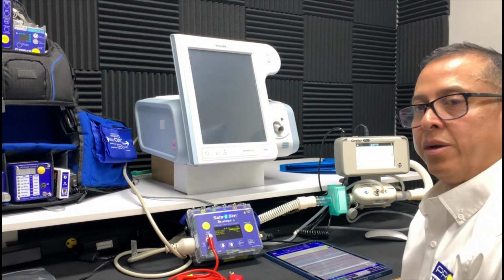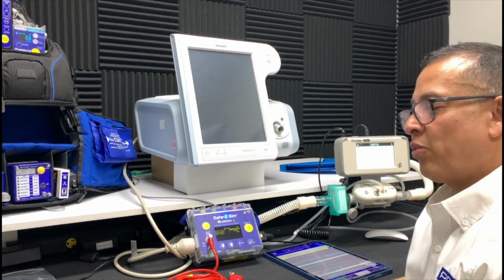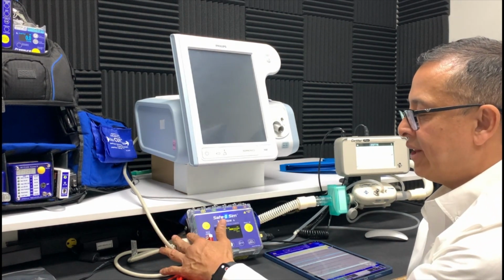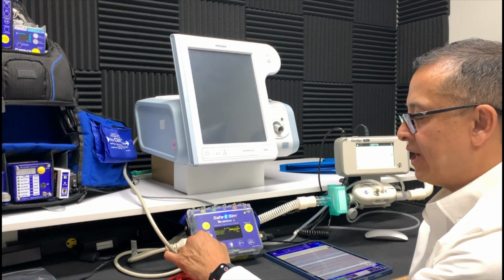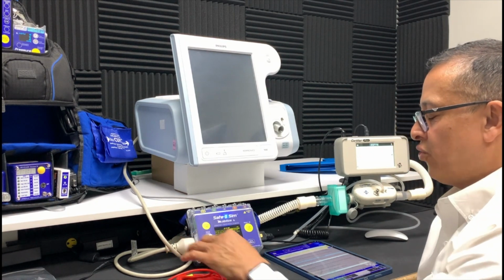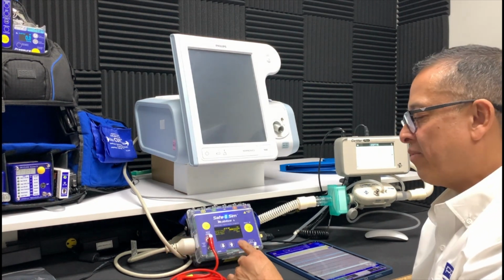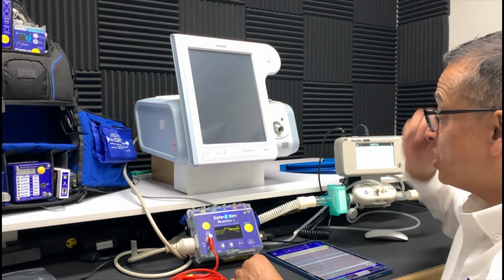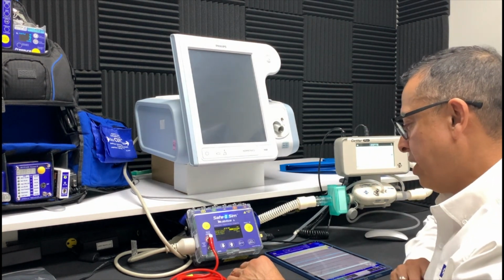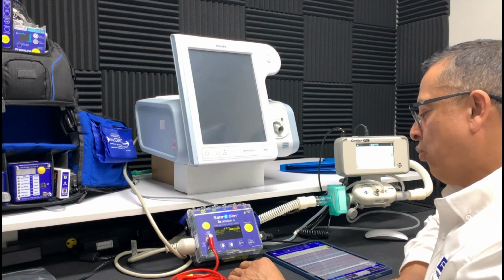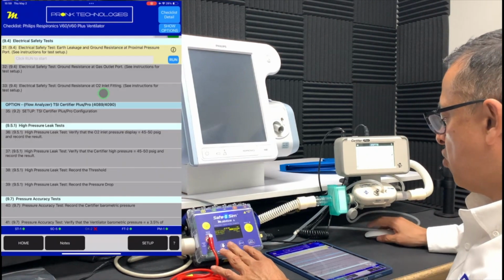So to run the electrical safety test, we want to make sure we hook up, of course, the ventilator to the electrical safety analyzer. We need to do the ground resistance test on a couple of different points, including the rear of the unit. So we're going to make sure we do those as well, and perform the electrical safety test according to the procedure.